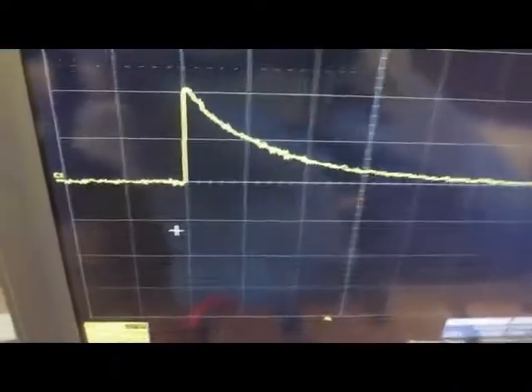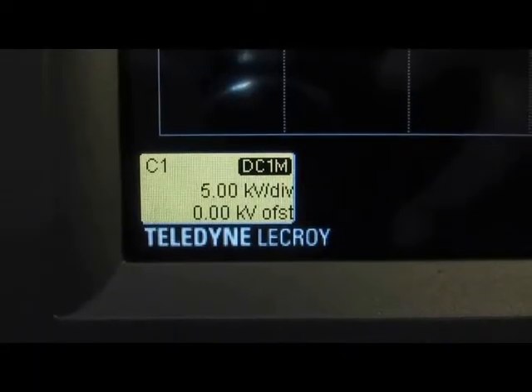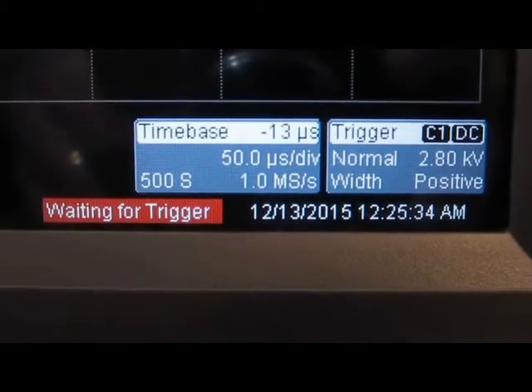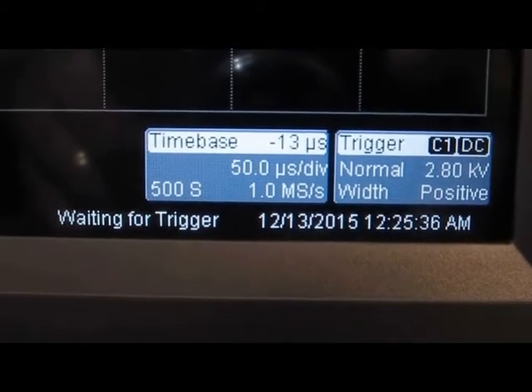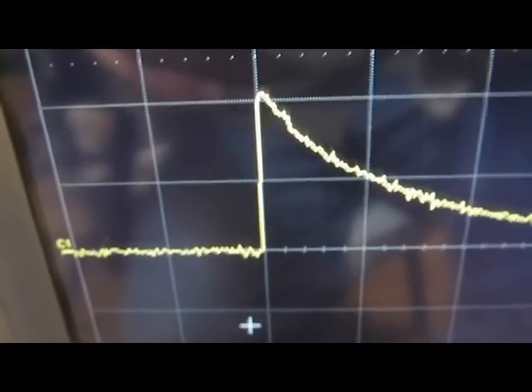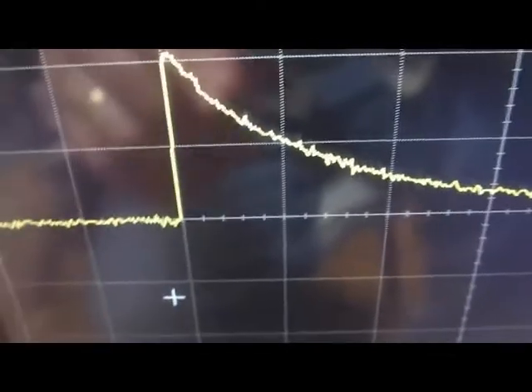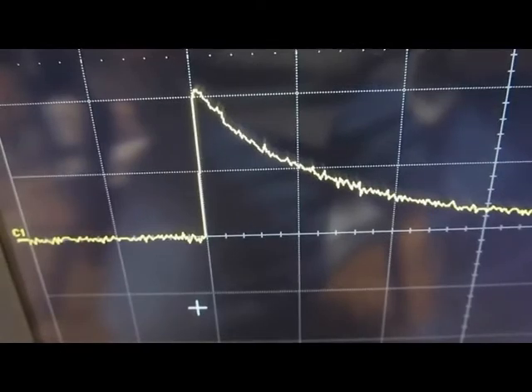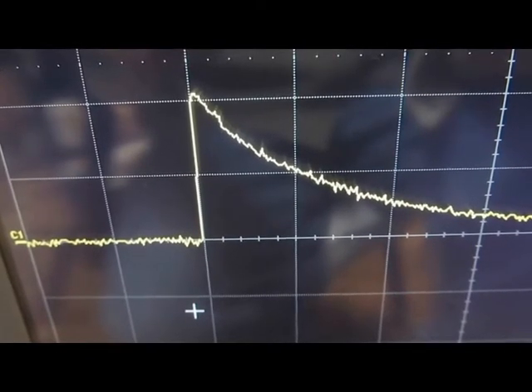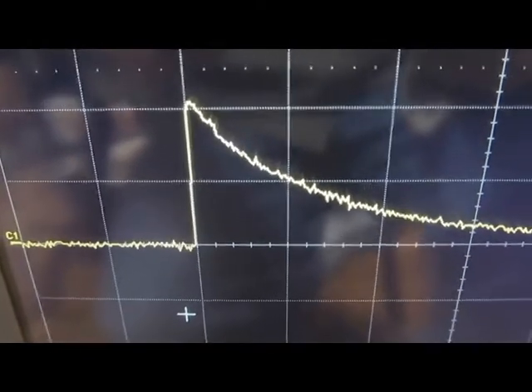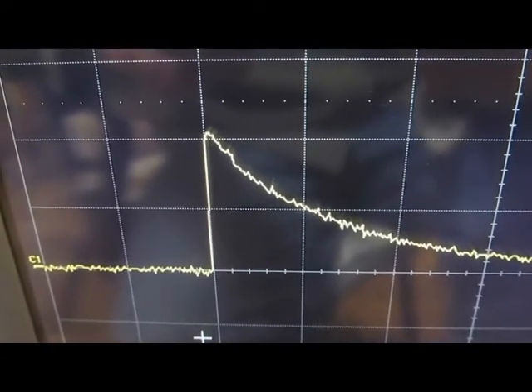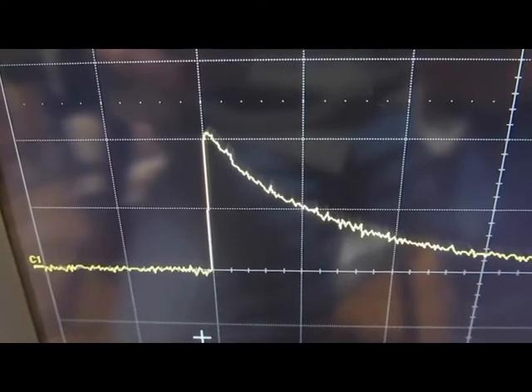I thought I'd show you the waveform off of it. As you can see here, we're looking at 5,000 volts per division, and this is 50 microseconds per division. You can see we're two divisions up, or roughly 10,000 volts, and we can see the full width half height is roughly 50 microseconds. And again, the reason I'm using the 50 microsecond full width half height is because that basically conforms to the IEC standard.